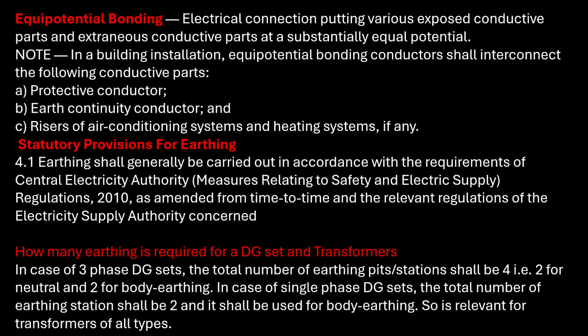In case of single phase DG set, the total number of earthing stations shall be 2 and it shall be used for body earthing. The body earthing is necessary so that a person touching part of any such equipment does not get the shock. And the neutral earthing is necessary to stabilize the voltage system. So suppose if it is disconnected, then there is likely to get 11 kV transferred to 433 medium voltage.